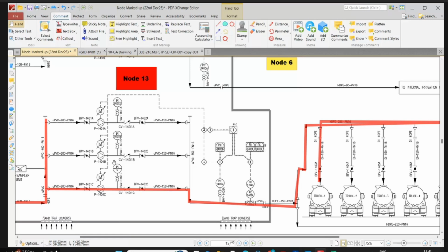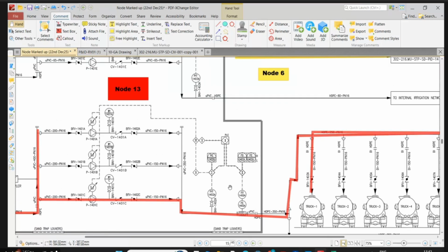Once you open this one, for example, you have pressure coming like 5 bar. Let us keep the pressure 5 bar. Then once you open one line, the pressure goes to 4 bar. So the first pump will work. And there is a connection between the flow reading and the pressure transmitter in the PLC. So based on any tanker opening, the pressure will go down, and it will control. The first pump will reach full capacity, then after that, because of the speed, the second pump will be integrated and it will adjust the speed of the pumps with the pressure.